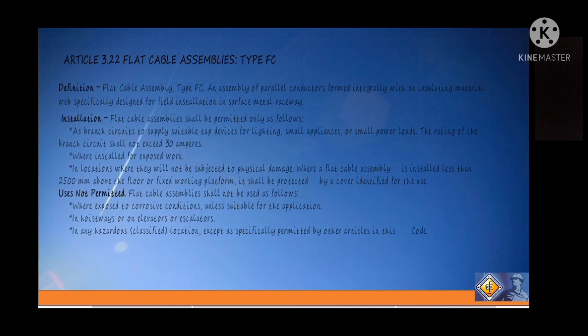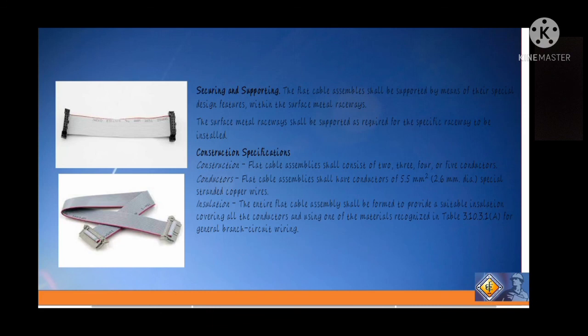So in terms of location, where they will not be subjected to physical damage, where a flat cable assembly is installed less than 2,500 mm above the floor or fixed working platform, it shall be protected by the cover identified for the use. So for the use not permitted naman, so where exposed to corrosive condition unless suitable for application, and in hoistway or an elevator or escalator, and also in hazardous location except as specifically permitted by other article in this code. So here are the pictures of our flat cable.